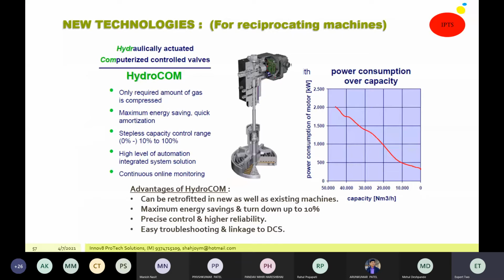Nowadays, for reciprocating air compressors, hydraulically actuated computerized control valves are provided, and this is the valve which can give you stepless capacity control and provide you the air as and when it is required, at the right quantity and right pressure.